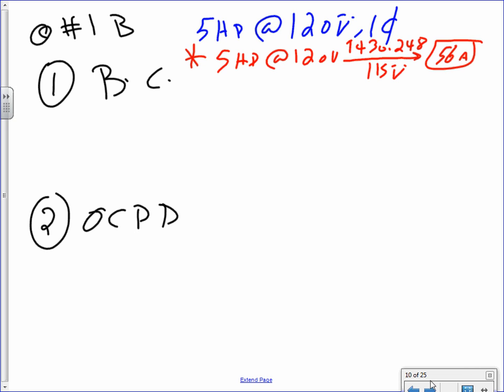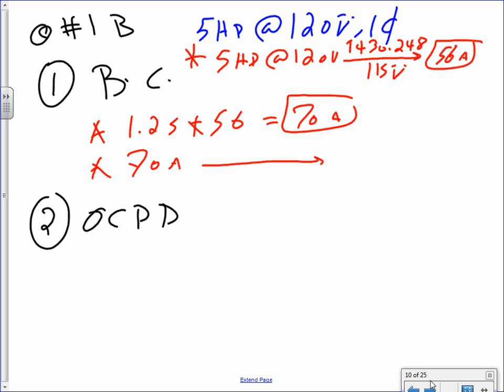Now, branch circuit, the same thing. Calculation very easy, guys. When you do branch circuit, 1.25, multiply this baby by 56. That will get you a 70 amp. And then you take the 70 amp to table 310.15 B16 under the 60-degree Celsius column. Why? Because it's Romex, and it's an NM cable, so that will get you number 4 AWG NMB.